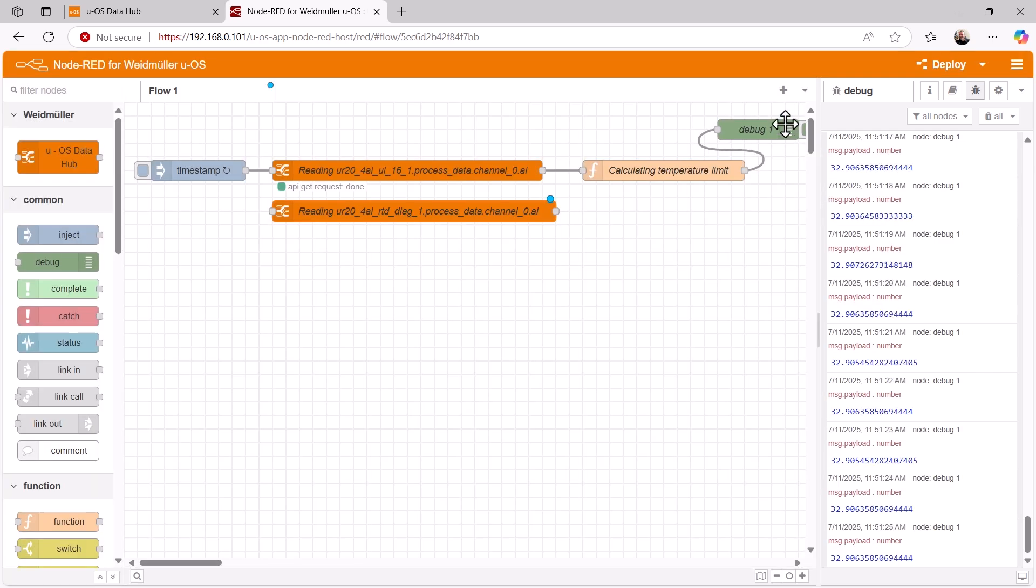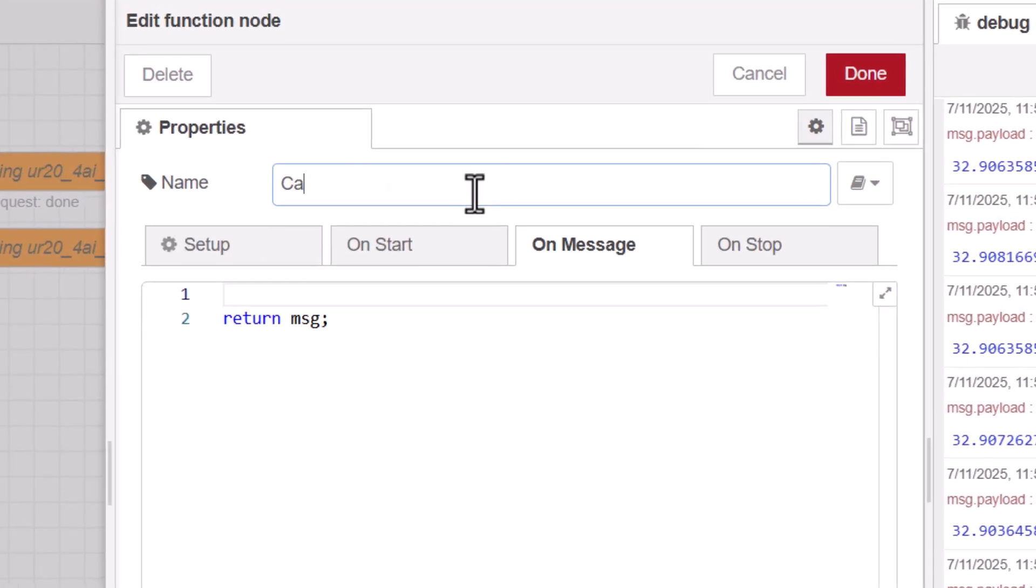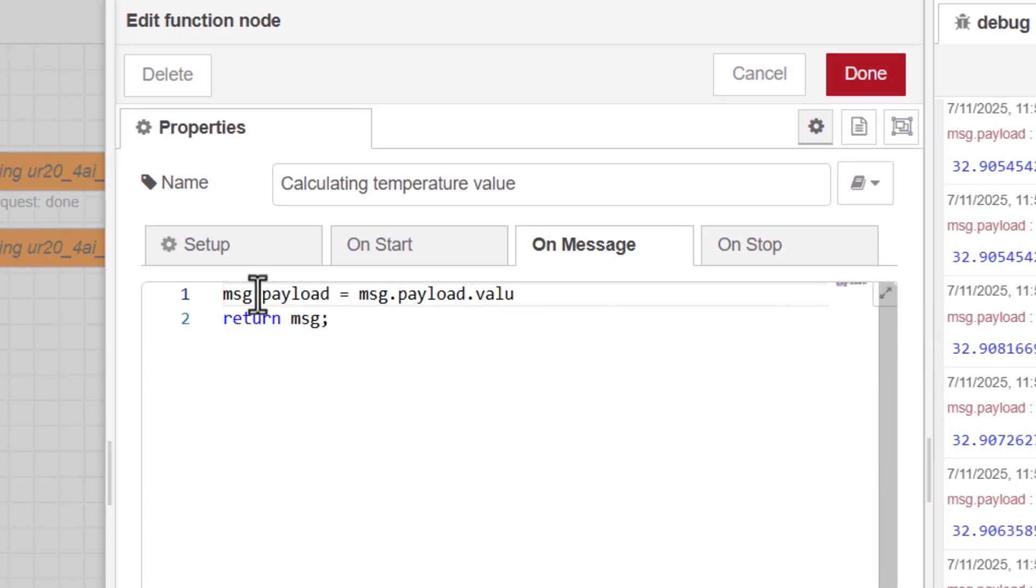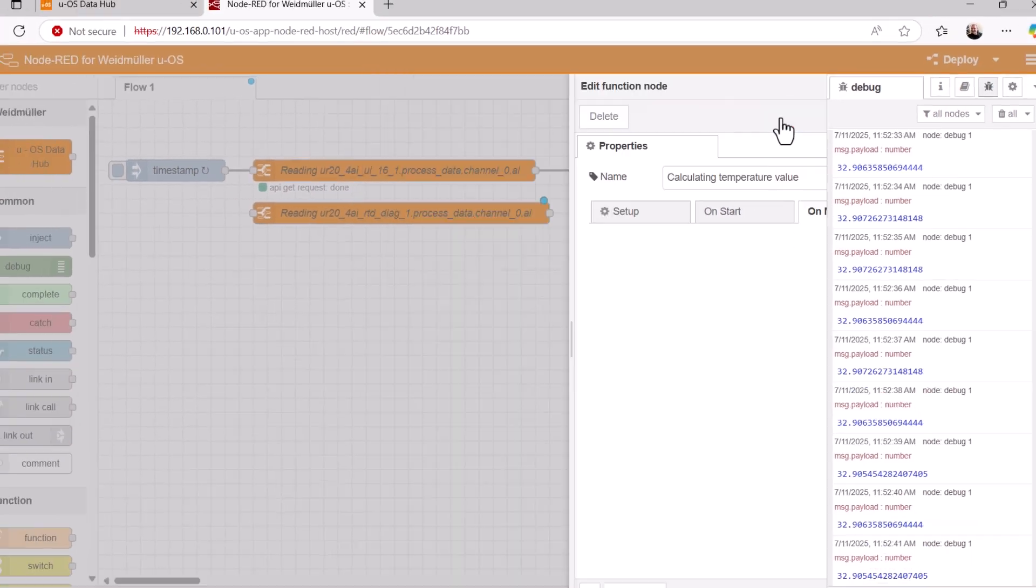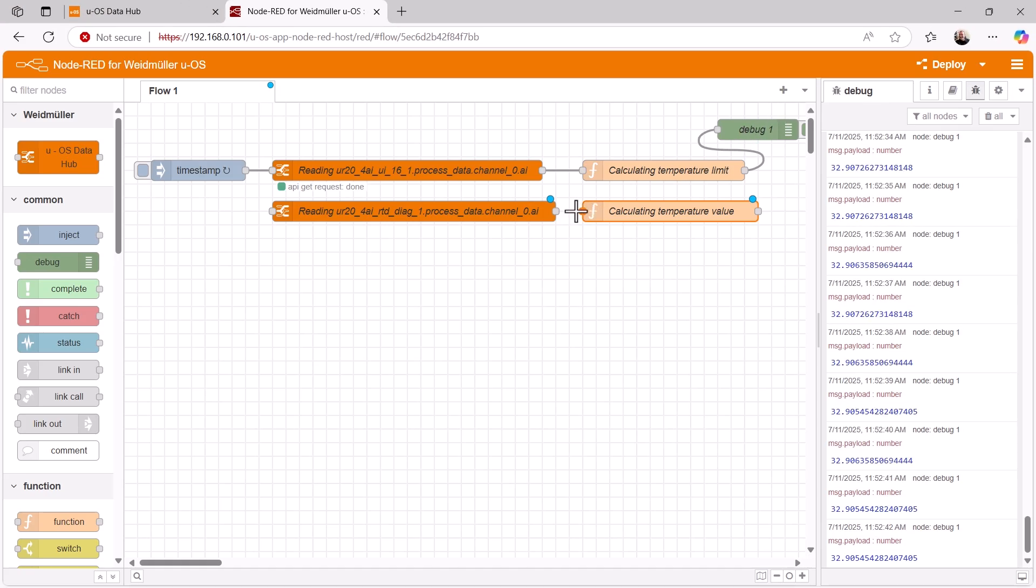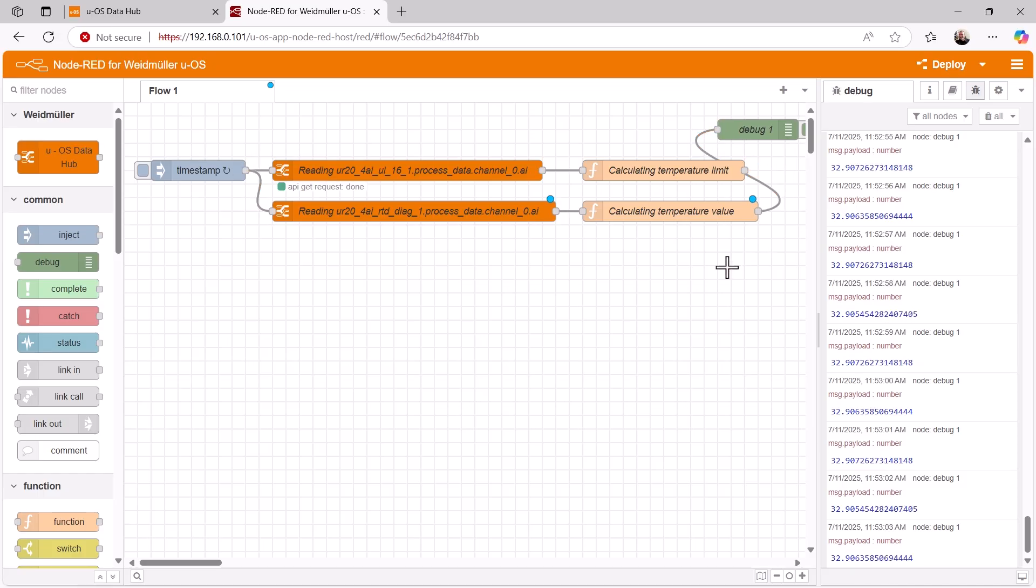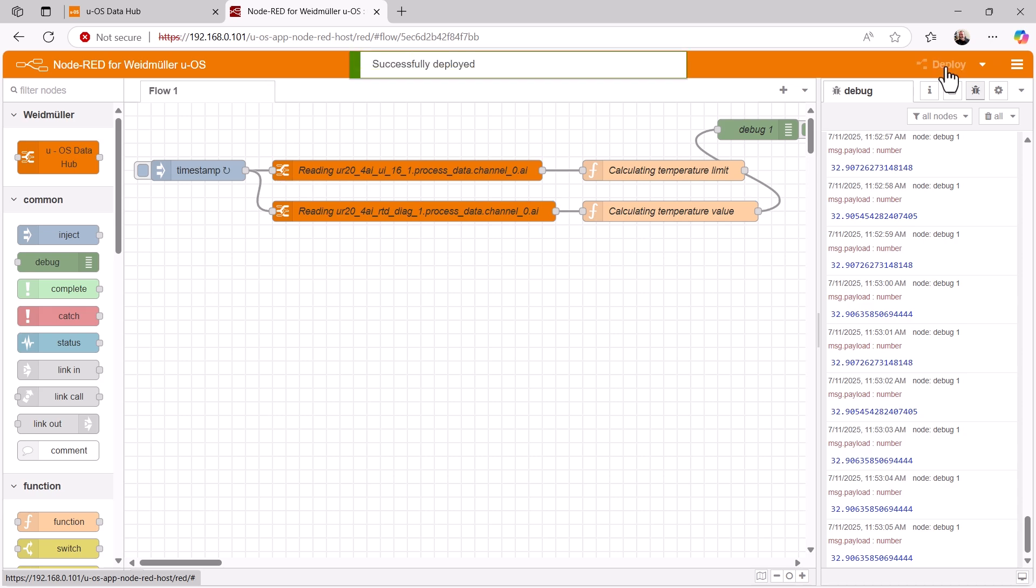Now we will also perform a conversion for this value using a function. The measurement module provides a temperature in tenths of a degree Celsius, so we simply divide the input value by 10 to transfer the actual temperature value as the output value. Now we just need to connect the nodes and also trigger the new DataHub node via the Inject node. We now connect the debug node to the new output, transfer the new flow and look at the result.